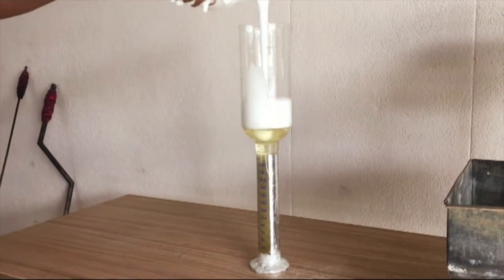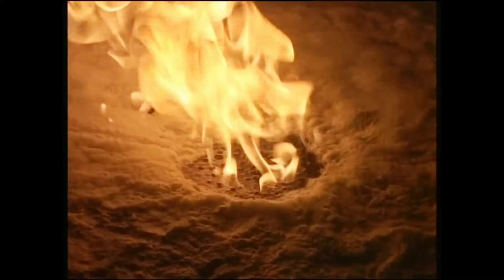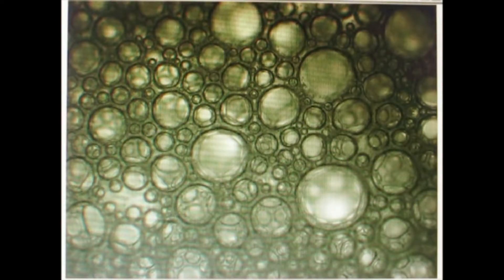Expansion ratio and drain time of firefighting foams are measured at a foam column height of 200 mm. Foam blanket on liquid fuel surface is just 30 mm thick. Drain times of several foam samples are experimentally investigated at constant expansion ratio and different bed heights.